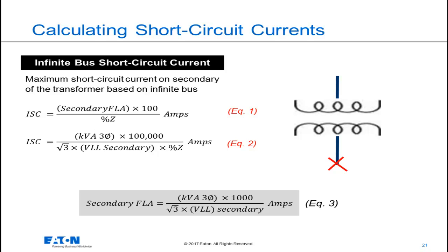The basic equation that we use is the full load amps times 100 over the percent impedance of the transformer. The secondary full load amps calculation equation that you'll use is seen in equation number three. If I combine equation number three here with equation number one, I get equation number two. This is how you calculate the maximum available short-circuit current that you can see on any transformer.